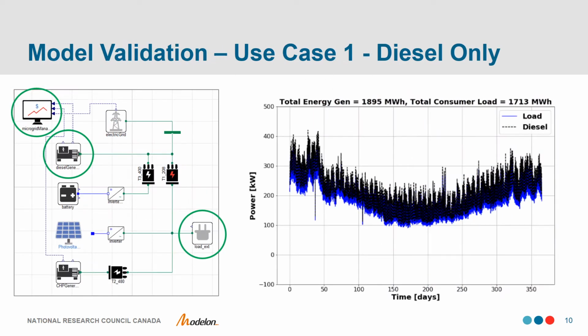The first simulation that we ran was for use case 1, operating in a diesel-only configuration. This included the diesel generator, the microgrid manager, and the Whale Cove load. Looking at the chart on the right, you can see that the diesel power is shown to correctly track load over the course of the simulation, with a slightly higher power output level than the consumer load to cover the upstream losses and station loads.